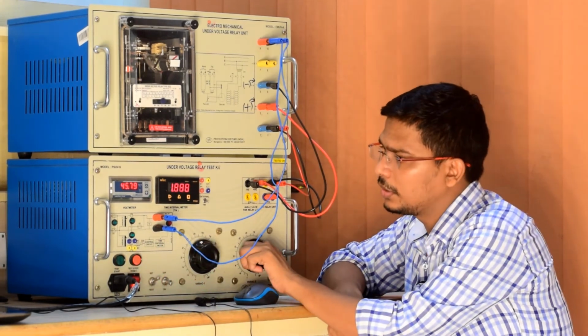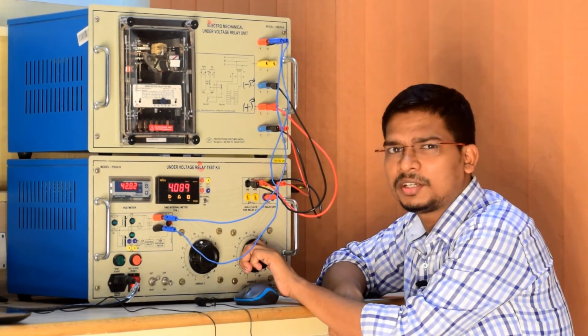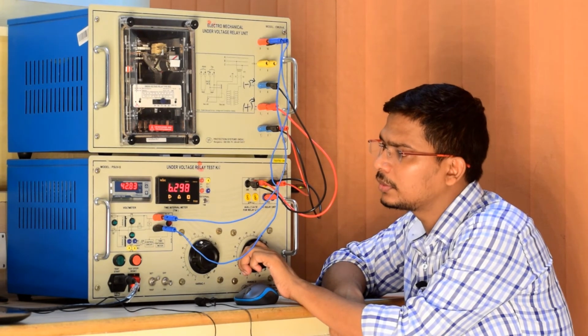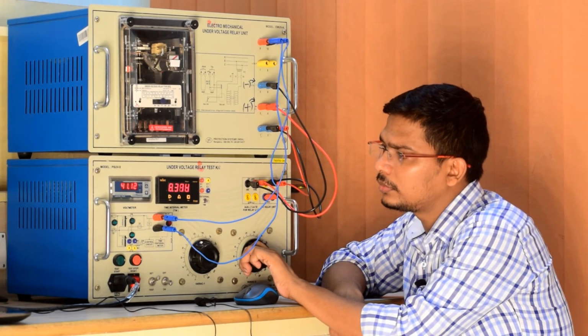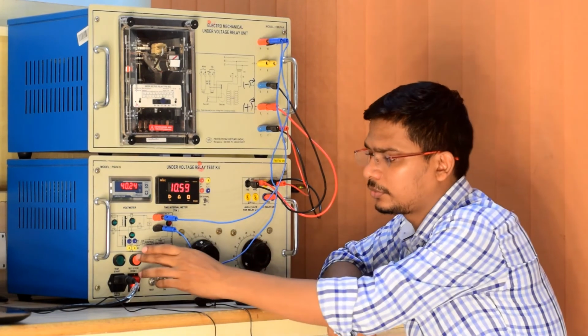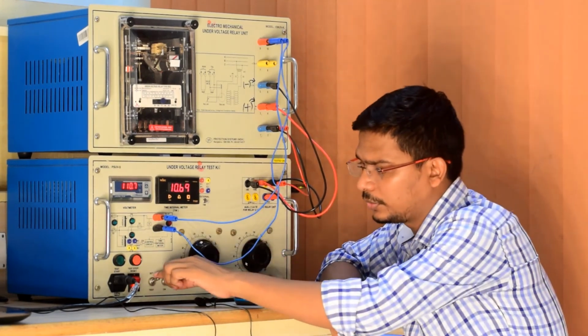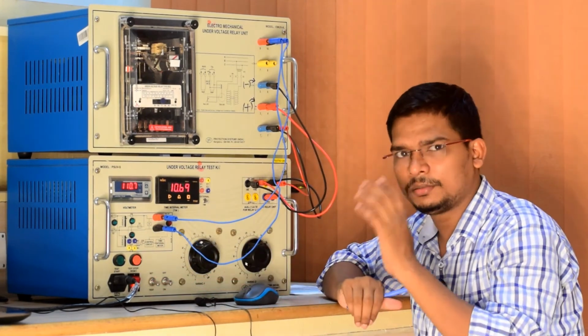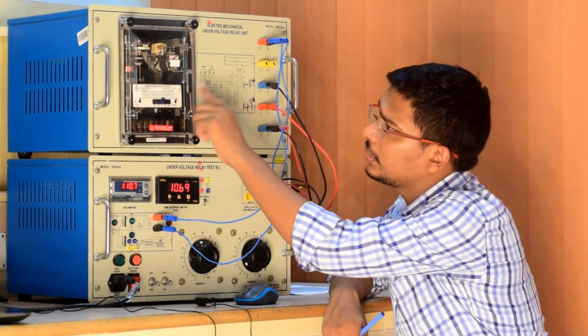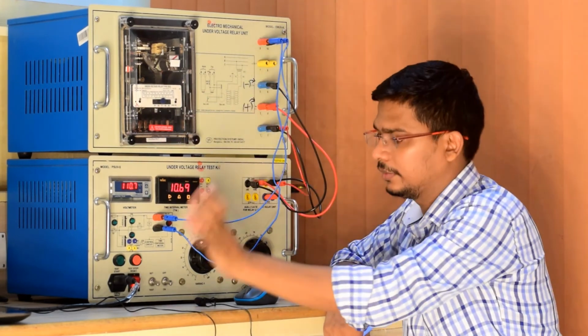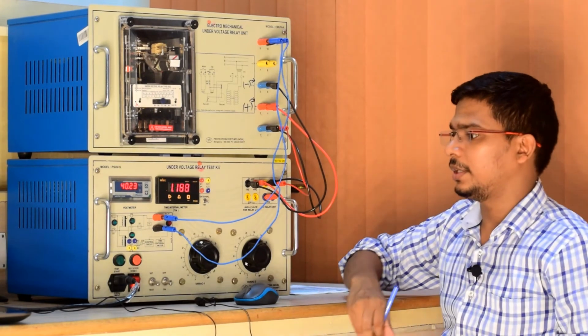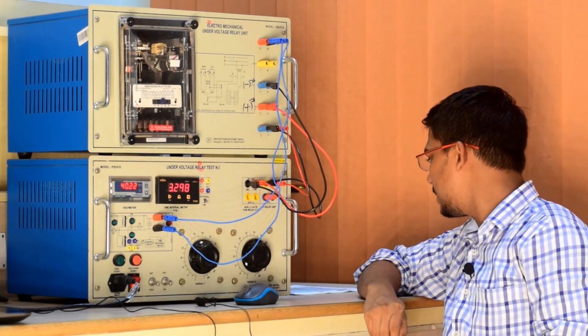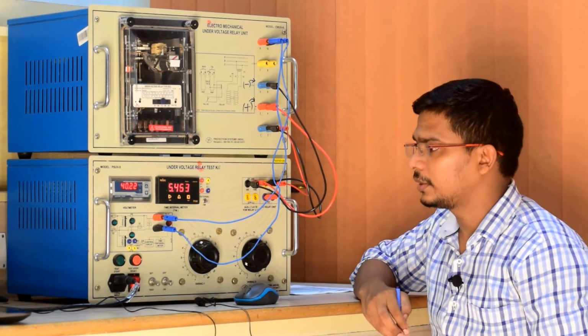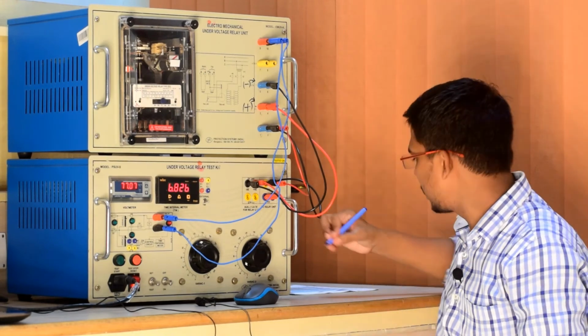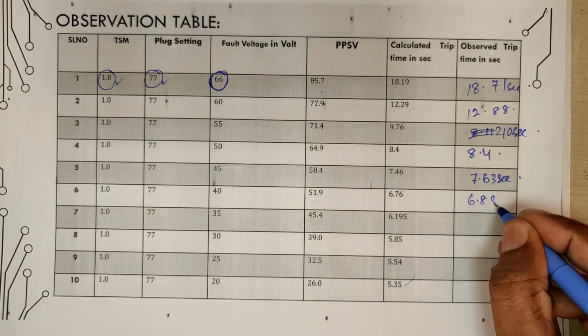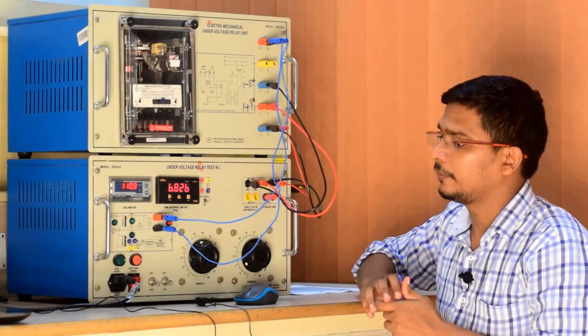Next observation is 40 volt. You are reducing 5 volt in each observation. So right now it is 40 volt. Turn off, put to test and wait a little. You have to see that the relay is standing still. Then start it again. Our expectation time is 6.76 seconds, and we got 6.8 seconds. Exactly our expectation is matching.